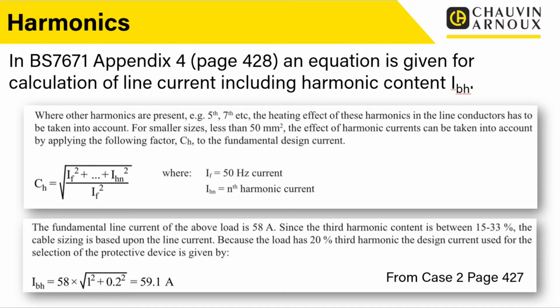So it goes on to say in here, where other harmonics are present, e.g. 5th, 7th, etc., the heating effect of these harmonics in the line conductors has to be taken into account. For smaller sizes, less than 50 millimeters squared, the effect of harmonic currents can be taken into account by applying the following factor. So we can work out this factor C, correction factor H, for harmonics. And we can look at the harmonic content, and the size of the fundamental, and we can use this equation to work out this correction factor.